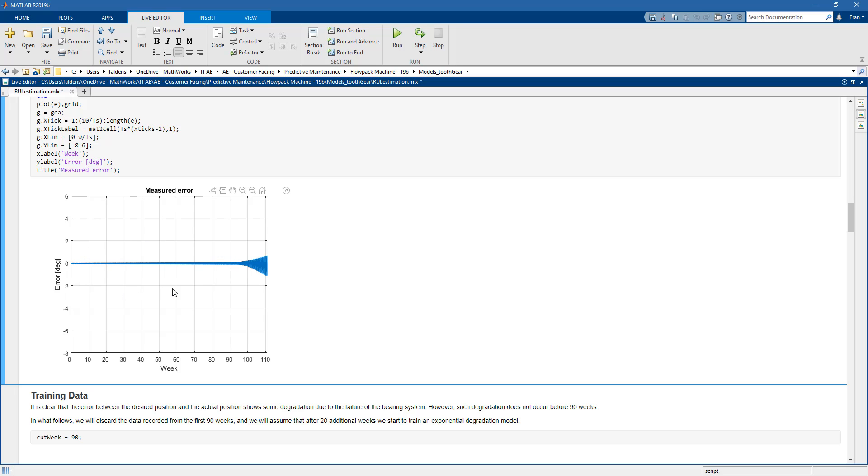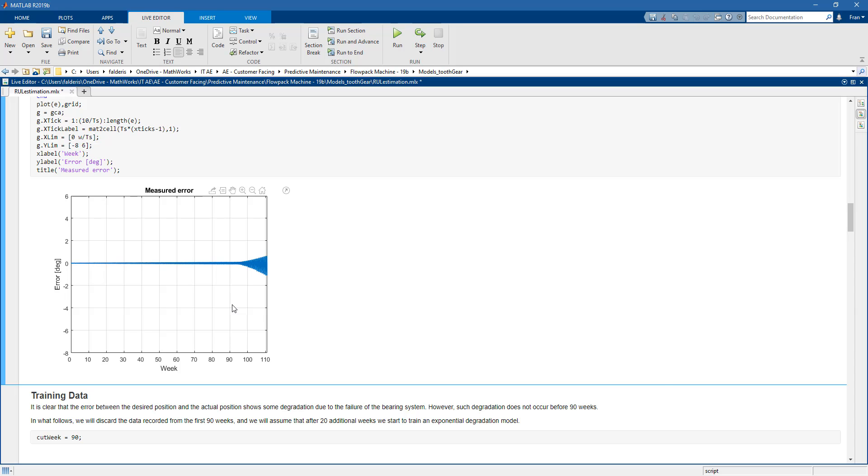As you can see here the first 90 weeks seem to be okay for our flowpack machine but then starting more or less from week 90 we can see that this error is starting to degrade and this might be an indication. So this might be an indication that something is not working well with our machine. Maybe it's not failed yet but there is something that we need to take a look at and monitor.